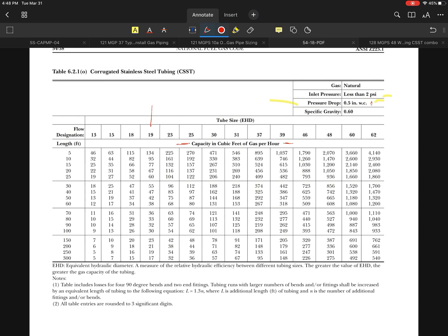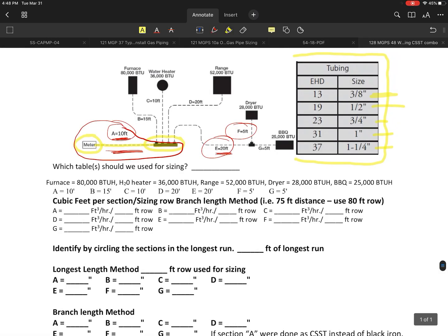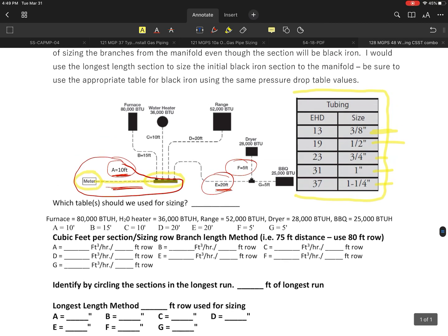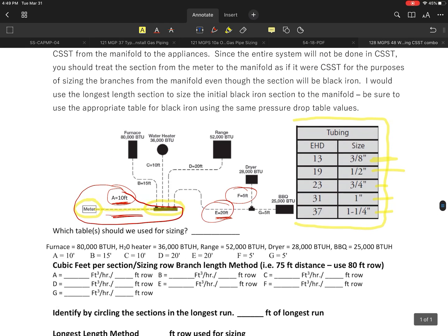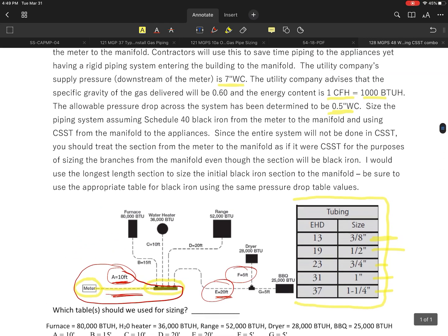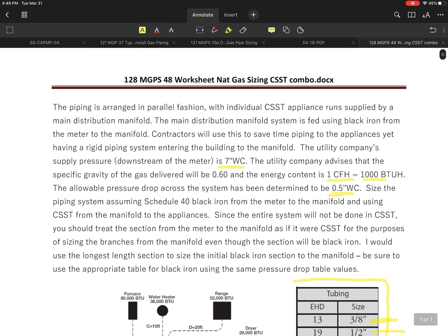It could have an impact on the resistance of that system. The CSST does have a lot more resistance. It's much higher than all of the other types of piping materials that I can think about. You just have to be prepared for that. That's a little bit on how to do that particular type of system.